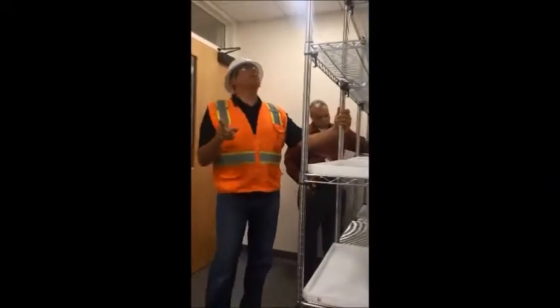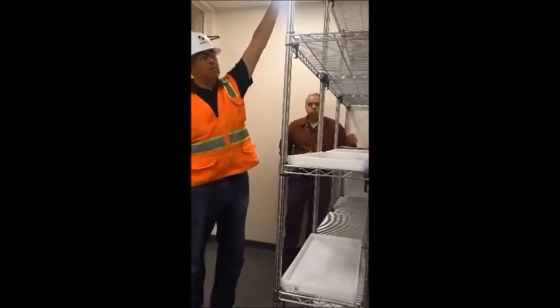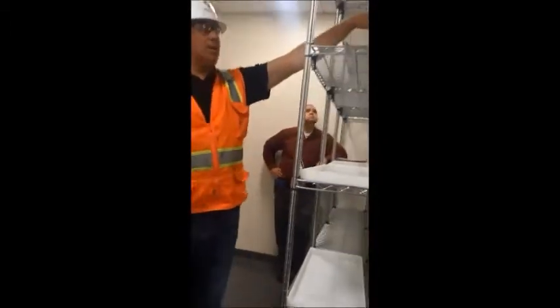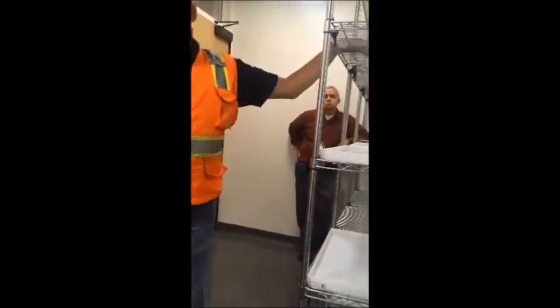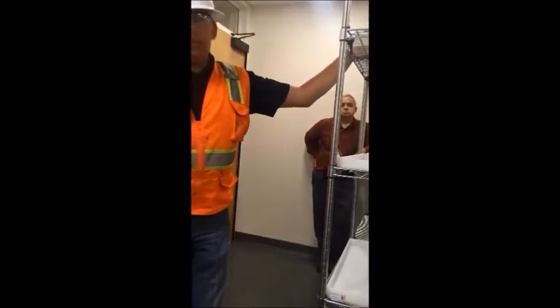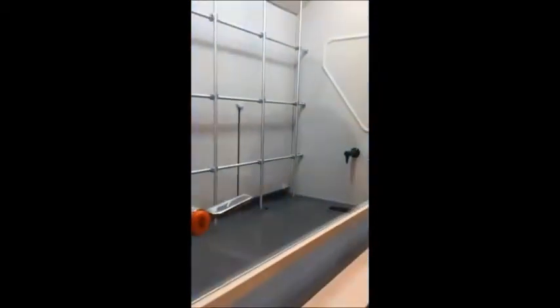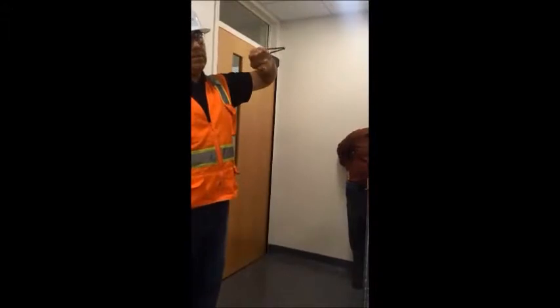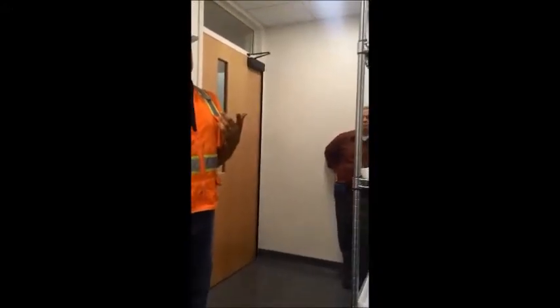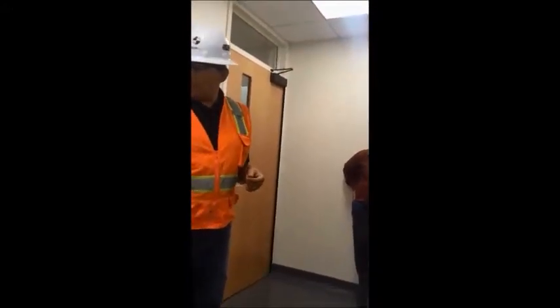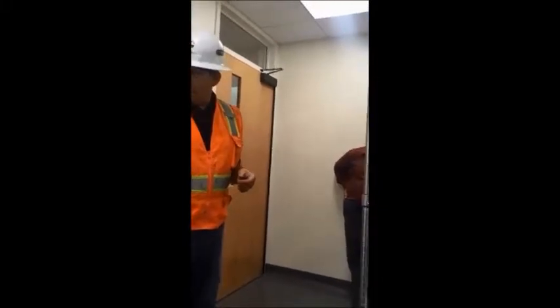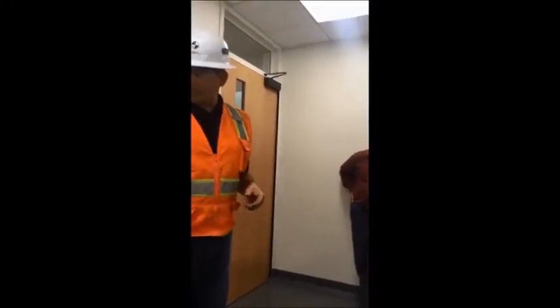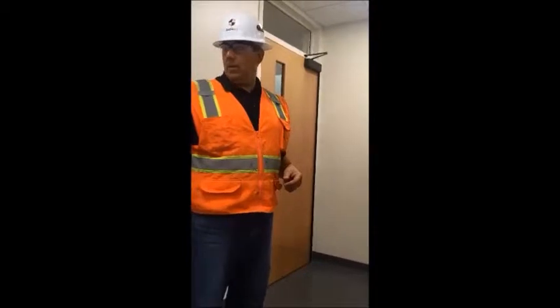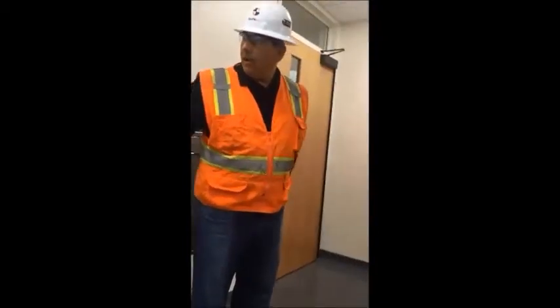So, you have a general exhaust, you've got chill beams with constant airflow, and then you have your lab hood. Again, the lab hood volume is in conjunction with the general exhaust. They work directly in reverse of each other. Again, as you increase or decrease the sash height, you see the velocity in feet per minute that's actually being pulled across the front of the hood. So they actually have a display on it.